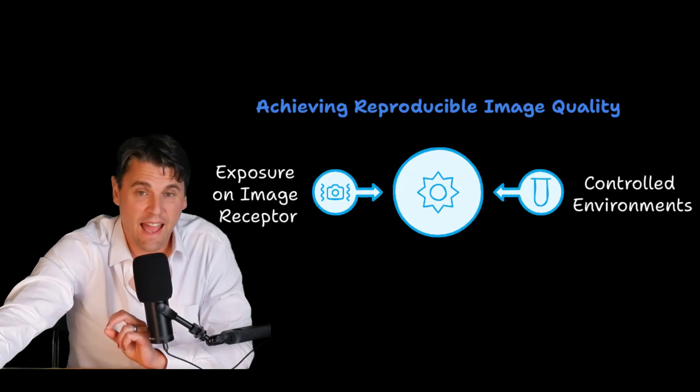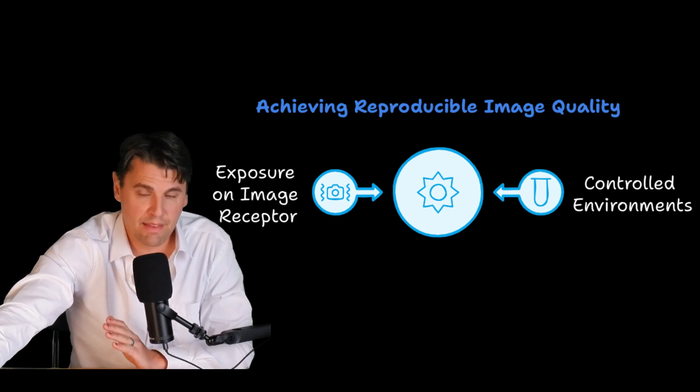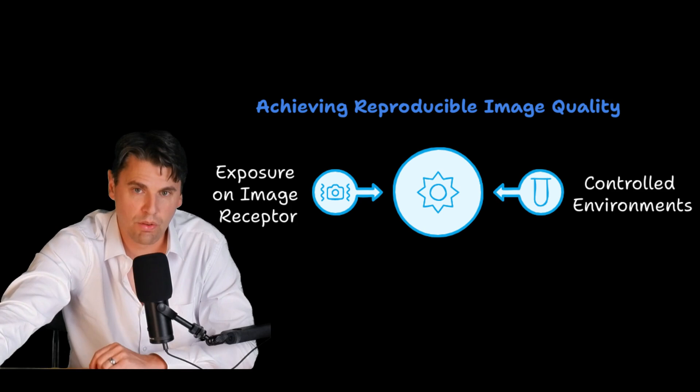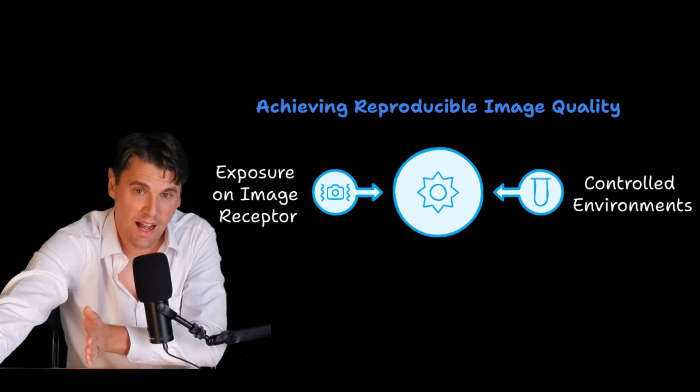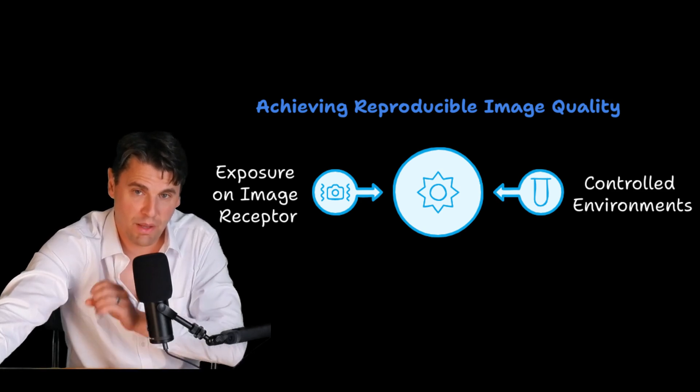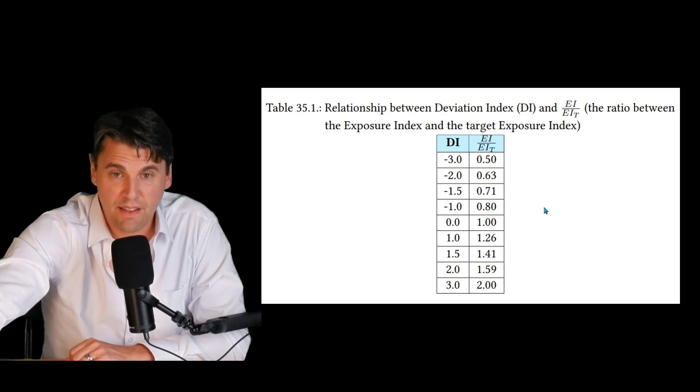In reality, it has been found that this is actually relatively difficult to do in practice, especially in situations where you're doing imaging at the bedside and in less controlled environments. We'd like to be reproducible with the exposure on the image receptor such that we can get reproducible image quality. These are just some example points like I had on the graph.